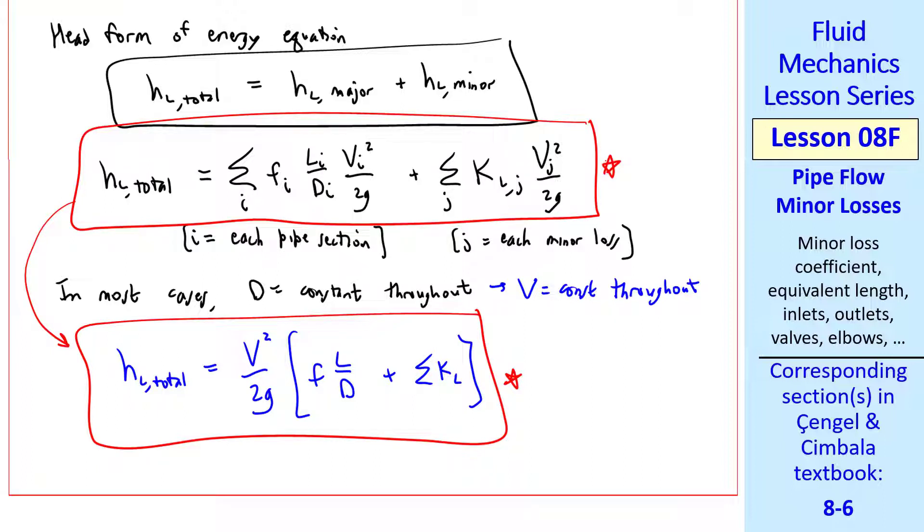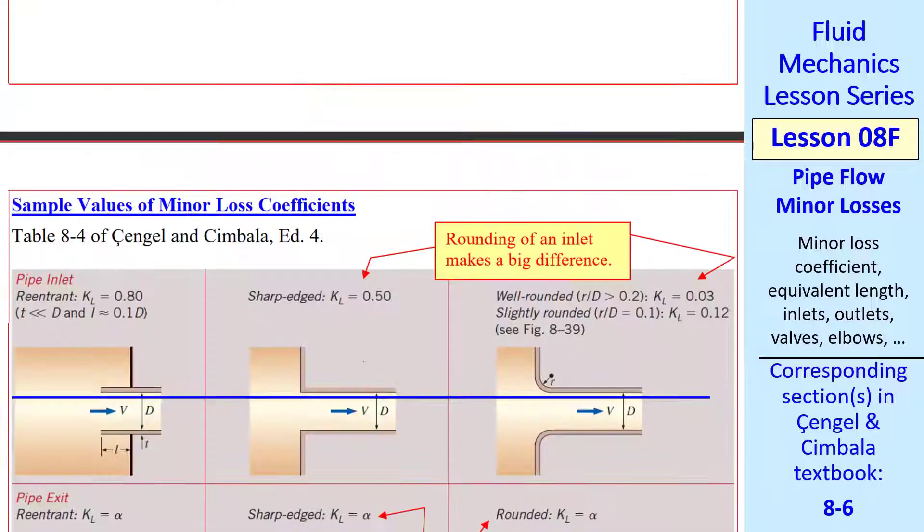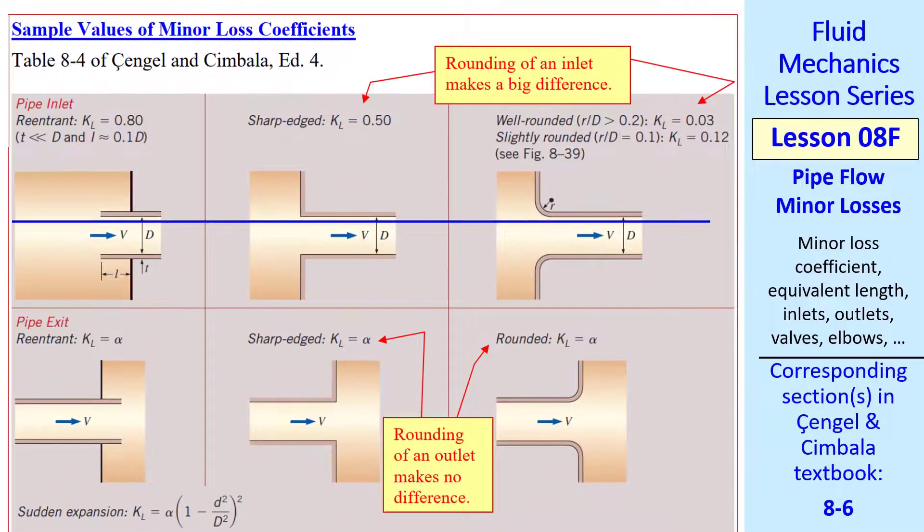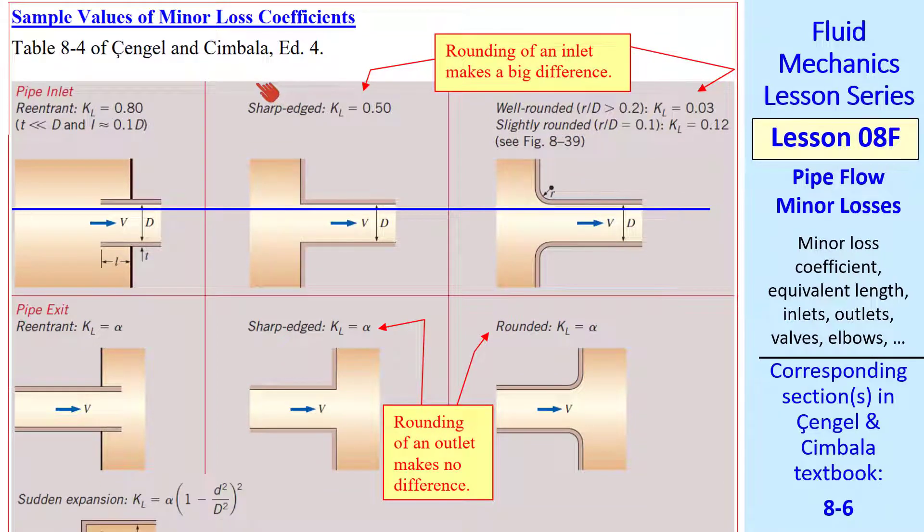Here are some sample values of minor loss coefficients from the Cengel-Cimbala textbook, and there are other publications that give KL for various minor losses. Here we show three different types of pipe inlet. A re-entrant pipe inlet, where KL is about 0.8. A sharp-edged inlet, where KL is about 0.5. And a well-rounded inlet, where KL can be greatly reduced, depending on how much rounding.